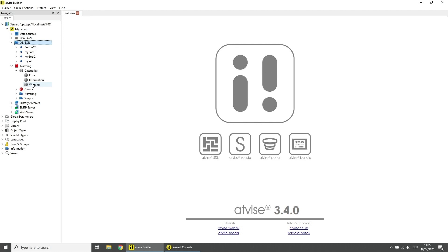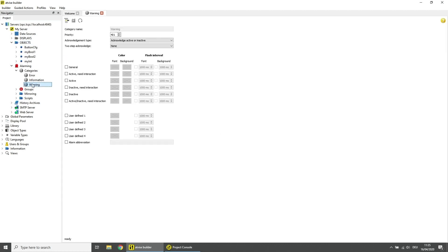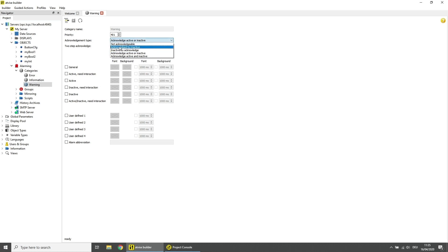Open the alarm category Warning with a double click. Change the acknowledgement type from Acknowledge Active or Inactive to Acknowledged by Inactive. Save the changes by pressing Ctrl+S or by clicking on the disk icon.